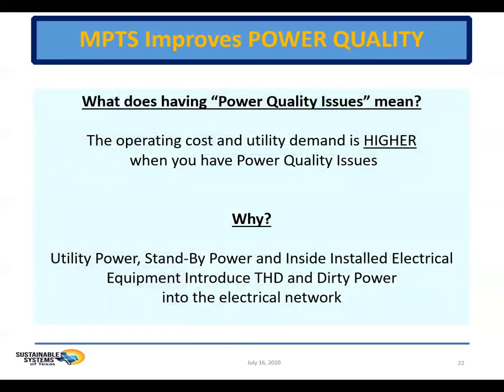All right, thank you, Brian. So we've learned that MPTS improves power quality. Having a power quality issue means your operating costs and utility demand are higher than they should be. Why? Because dirty power directly from the utility, dirty power from your standby gensets, and dirty power created by all the electrical equipment you have installed throughout your whole facility is affecting your power quality.